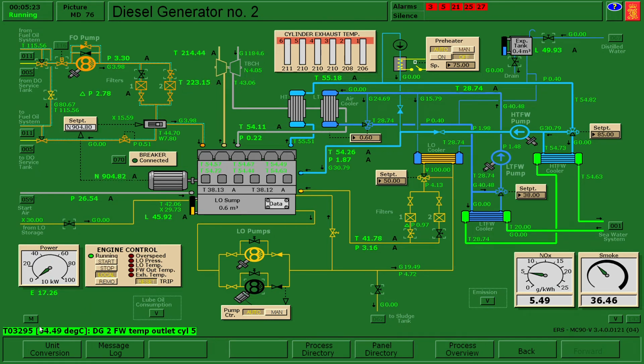And you can see this letter M here, which will open up malfunction pages. Just open that up, acknowledge the alarm, and then silence. And then we're just gonna go ahead and reset DG2 FO filter 1 dirty, DG2 FO filter 2 dirty, and our FO pump alarm. Okay, so we've reset those three. Close the malfunction page. Change over again. Just close this filter and open this filter again.